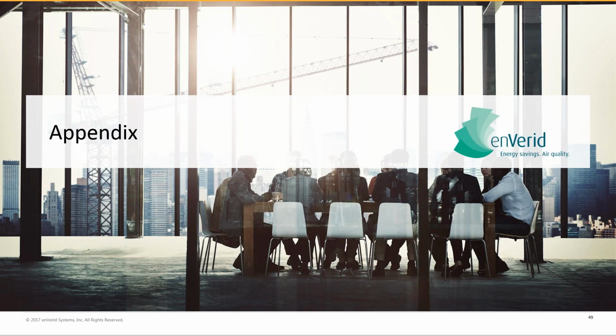It is like a two-lever system in the fact that if you wanted to incorporate fewer HLRs, fewer EnVerid units, you could do that, and you could design for a building to have more outside air, or you could try to drive that outside air down to minimum by incorporating more HLRs. So it's not one or the other. It's essentially a combination of outside air and HLRs. On average, we see about a 60% reduction in outside air for one HLR for every 150 to 180 occupants.